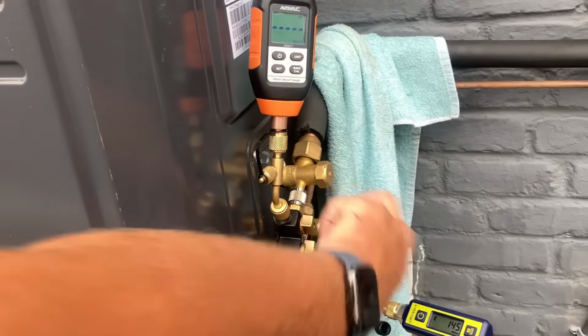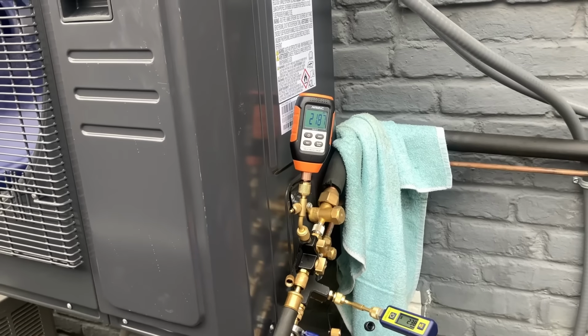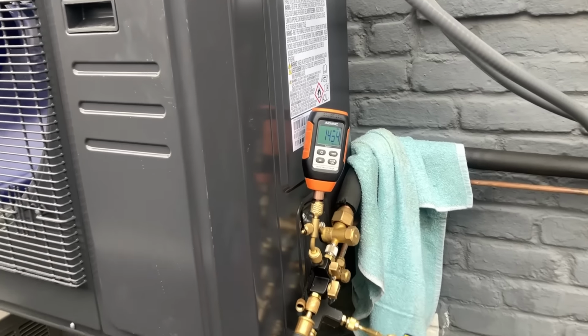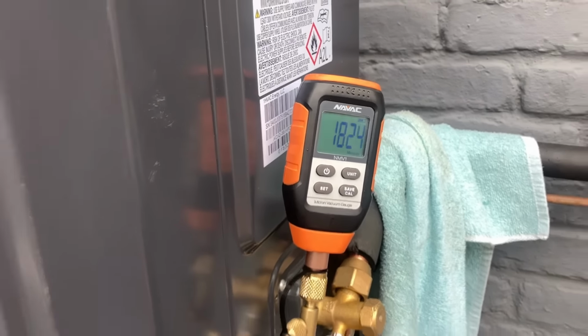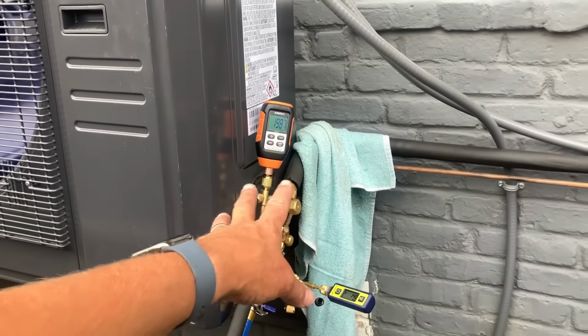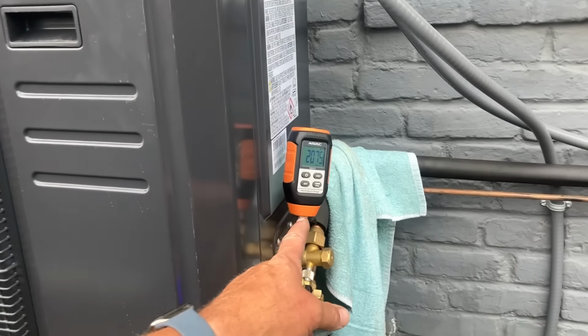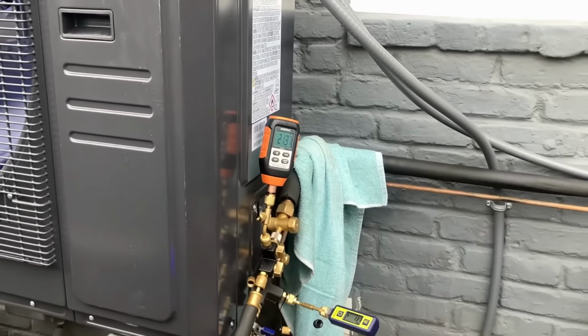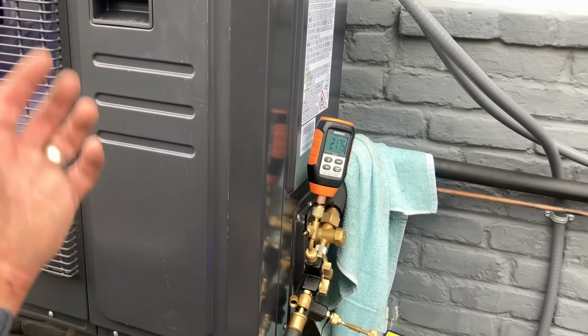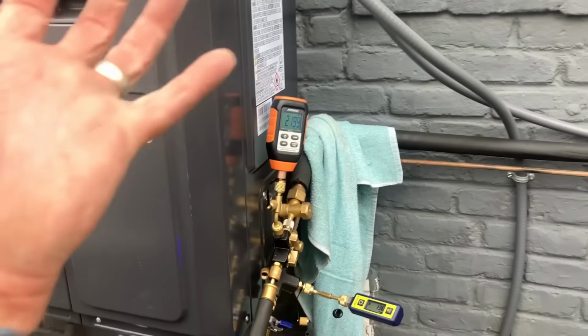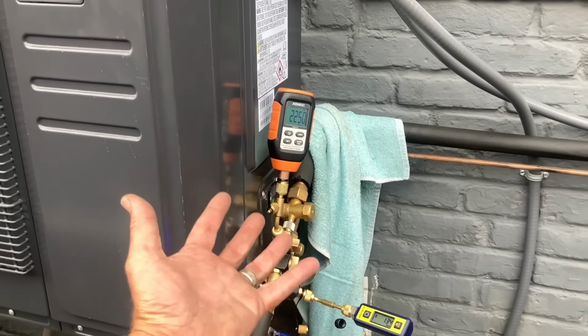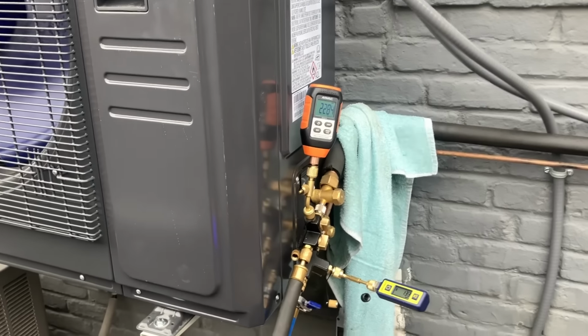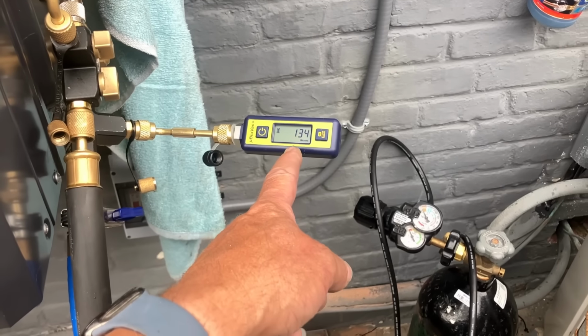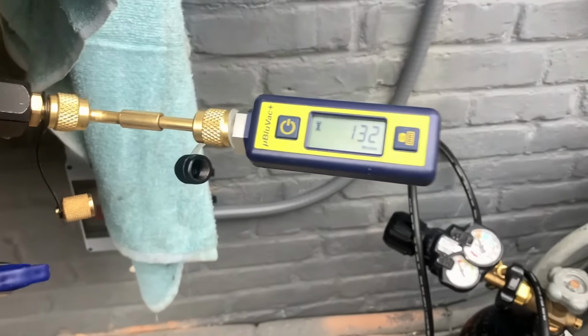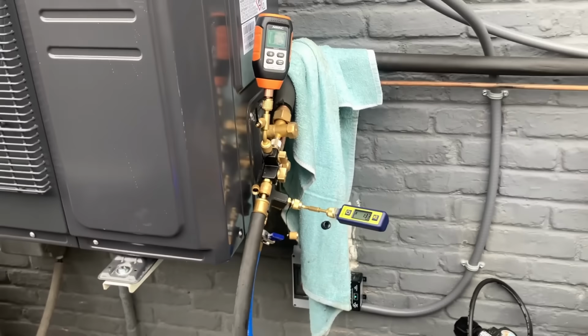All right, let's open it up again. See? Spazzing out. What are you spazzing out for? If that was accurate, that's moisture boiling off, the vacuum pump pulling a deeper vacuum. Moisture boiling off, expansion, that moisture expands. Was it like 30,000 times its size, right? And then it vacuums back down again. But I trust that. 133, 134, 132 microns.